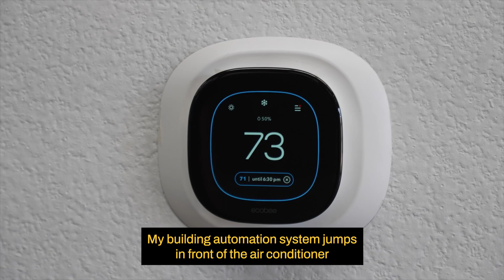At 4 o'clock in the afternoon, my building automation system jumps in front of the air conditioner and takes the compressor offline. It uses the fan to continue wafting air through the building and through our thermal storage product, which is cooled by our 62-degree ice, providing literally free cooling.